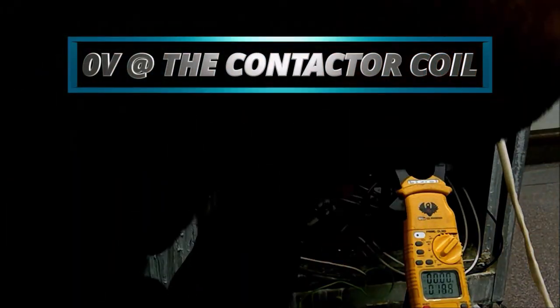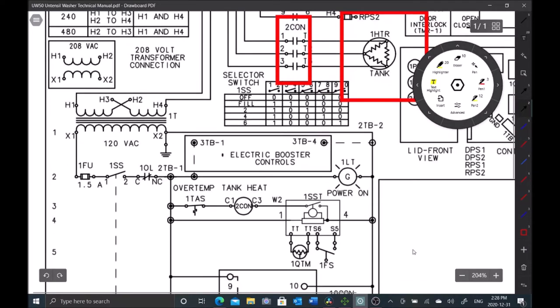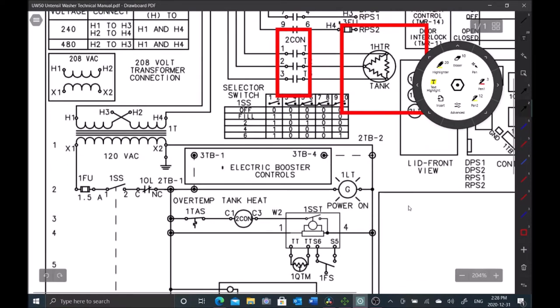I'm going to go test this contactor coil. Sorry the angle is pretty bad here. I am getting zero volts at that coil. I do not have power at the contactor coil.